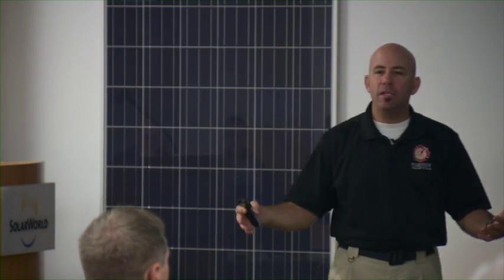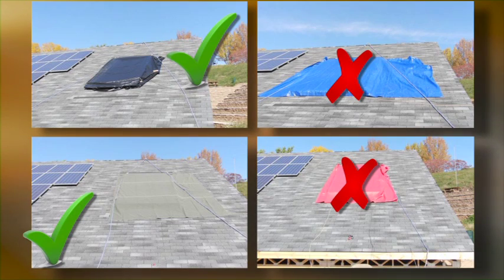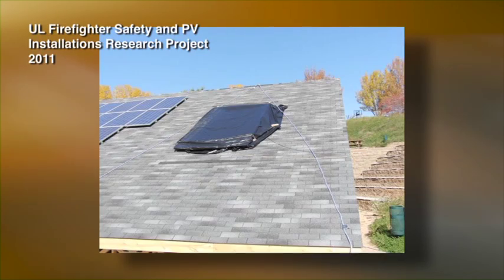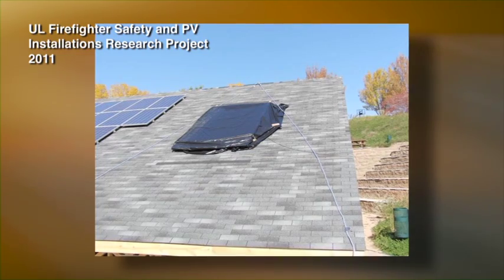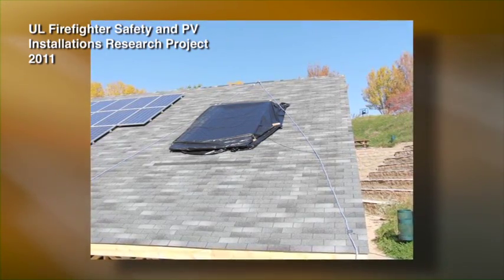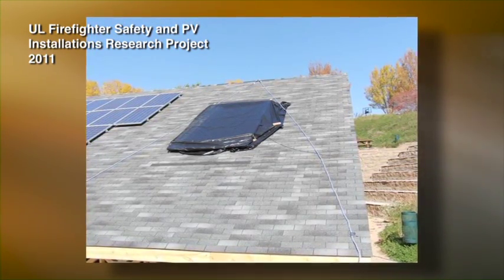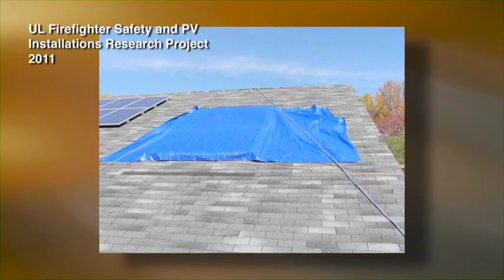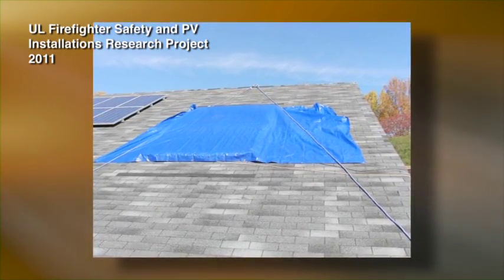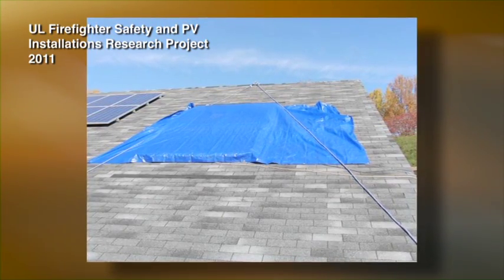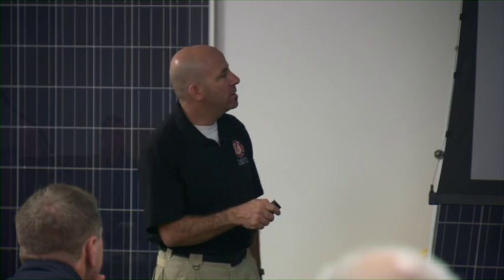So what we did was we tested several different common salvage cover materials. We took a black visqueen, one layer of it. We still got 33 volts, just light kind of getting in from the corners, but no current. All right, safe. So black works great, but you've got to secure it. One gust of wind. Any tarp you really have to secure. The blue polypropylene tarps, anybody use those? It's almost full voltage and 2.1 amps. Blue polypropylene tarps do not work.